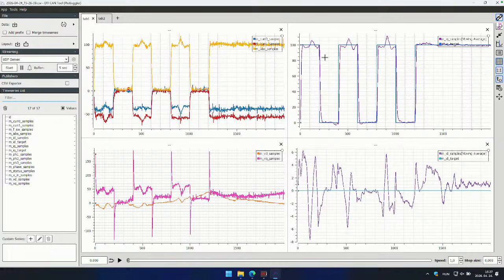As you can see, we have injected step responses, and we can observe that the actual IQ value follows the target really well. So in this case, we can say that okay, the current controller performs very well. If you see that the actual value goes above the target or below, then you have to make adjustments in the motor parameters, increasing or decreasing it, depending on whether it's too fast or too slow. And let's say that it's validated.